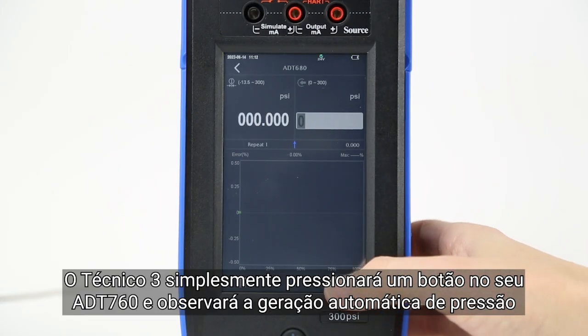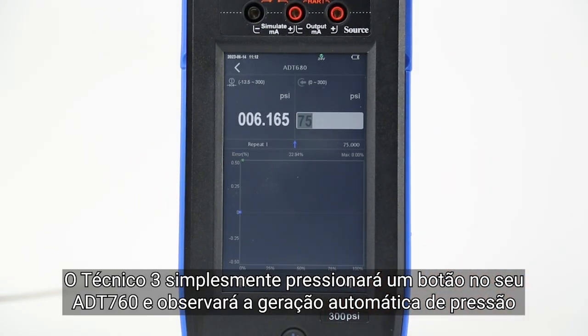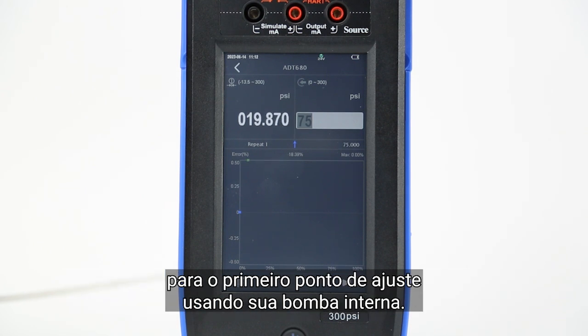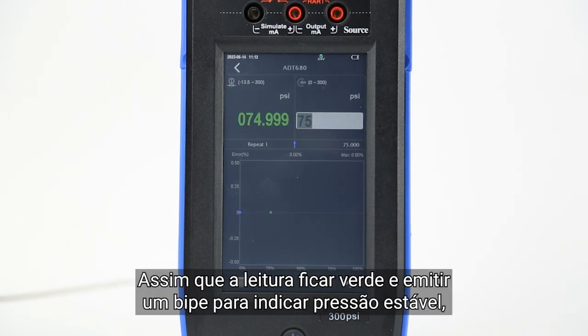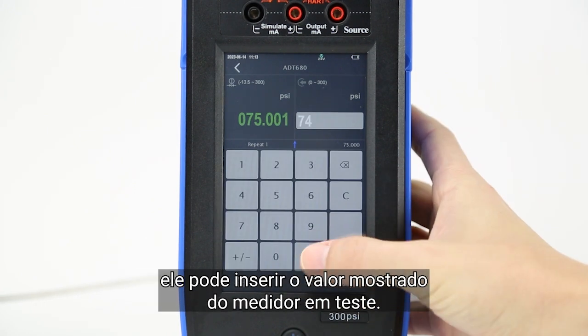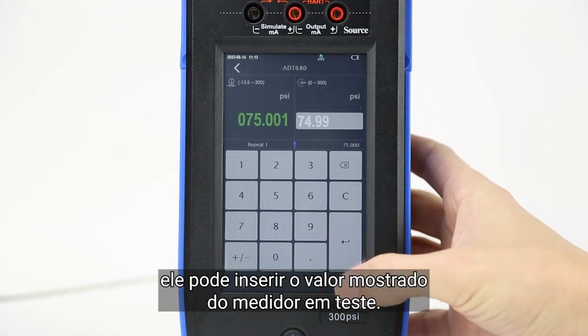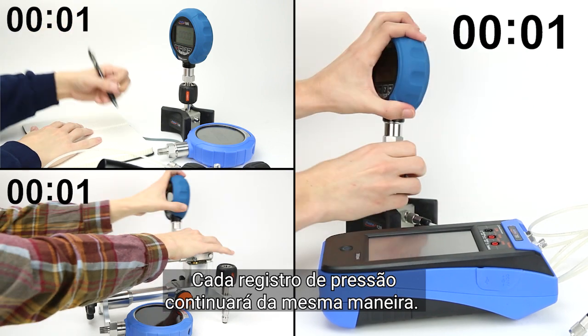Technician 3 will simply press the play button on their 760 and watch it automatically generate pressure to the first set point using its internal pump. Once the reading turns green and beeps to indicate stable pressure, they can enter the value shown on the gauge under test. Each pressure recording will continue in the same manner.